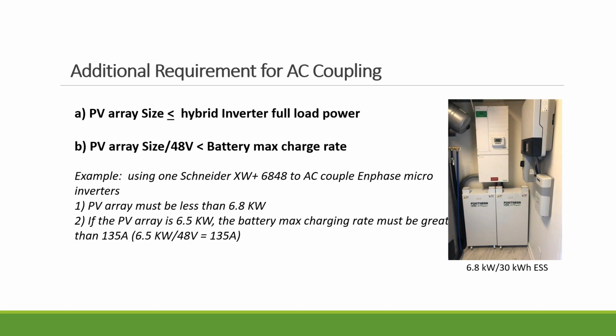And then rule number two, the same idea. If you have no load, let's say, and you use the PV production to charge the battery, in that case you want to make sure the battery bank is big enough to handle that charging amperage from the PV array. As an example, if the PV array is 6.5 kW, the battery maximum charging rate needs to be greater than or equal to 135 amps. So you take 6.5 kW divided by 48 volts, which equals 135 amps. That way you can make sure the battery bank can handle the PV production at its peak without causing any problems.